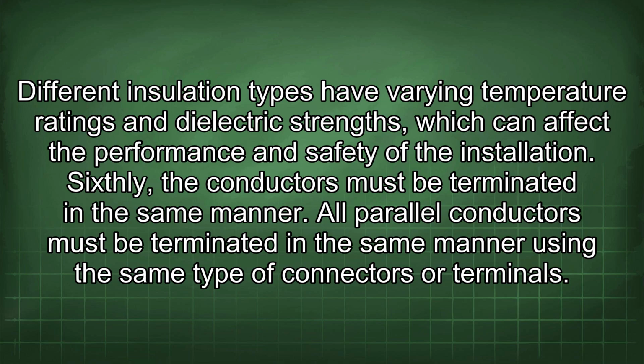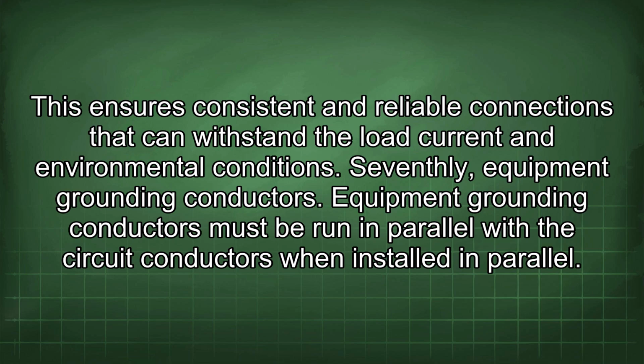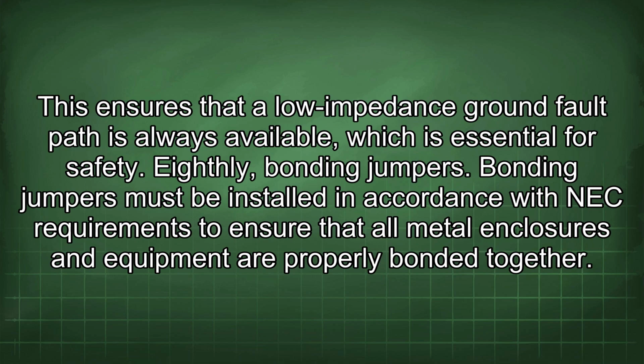Sixthly, the conductors must be terminated in the same manner. All parallel conductors must be terminated in the same manner using the same type of connectors or terminals. This ensures consistent and reliable connections that can withstand the load current and environmental conditions. Seventhly, equipment grounding conductors. Equipment grounding conductors must be run in parallel with the circuit conductors when installed in parallel. This ensures that a low impedance ground fault path is always available, which is essential for safety.